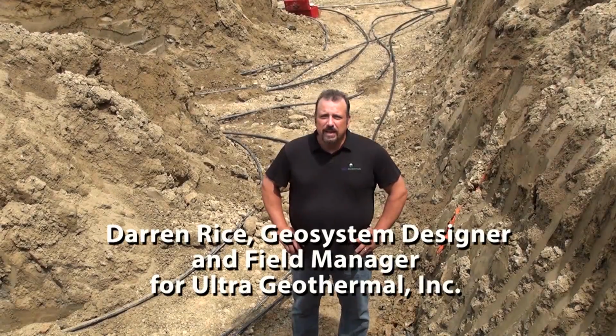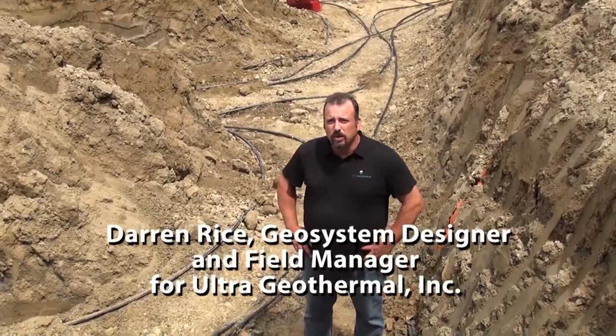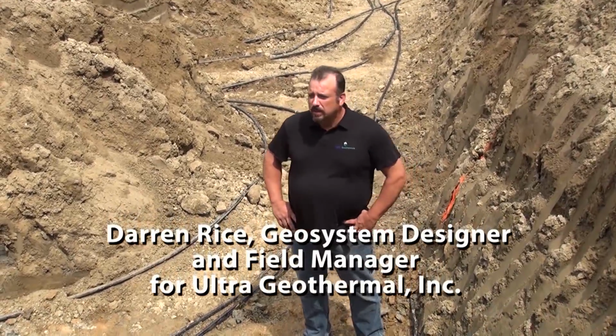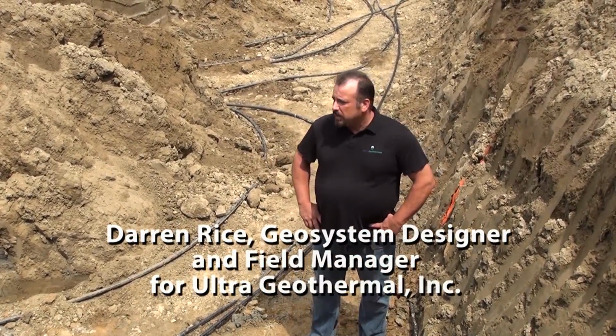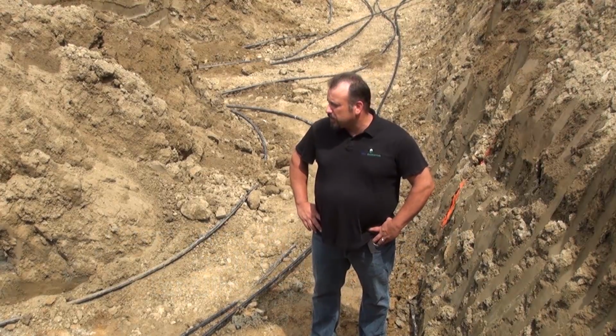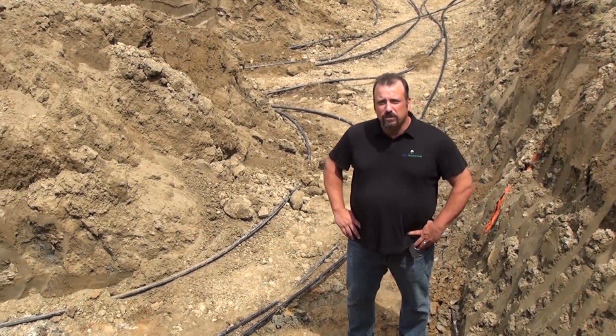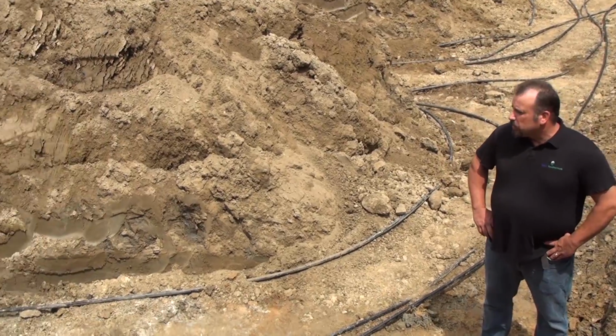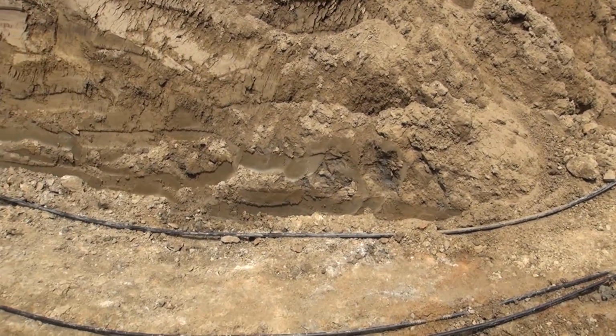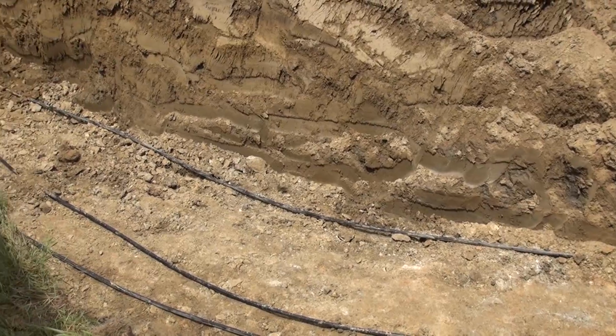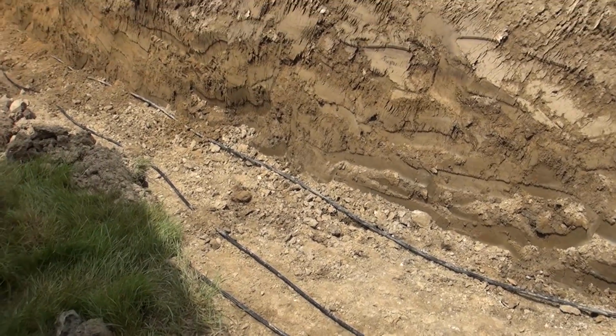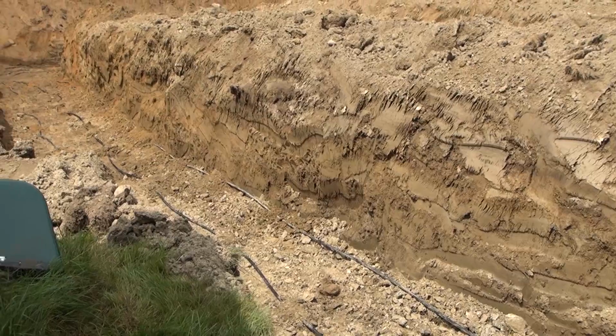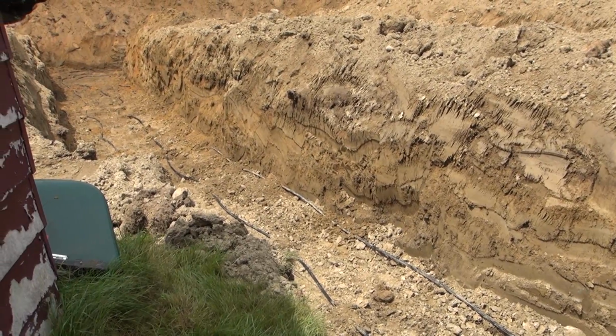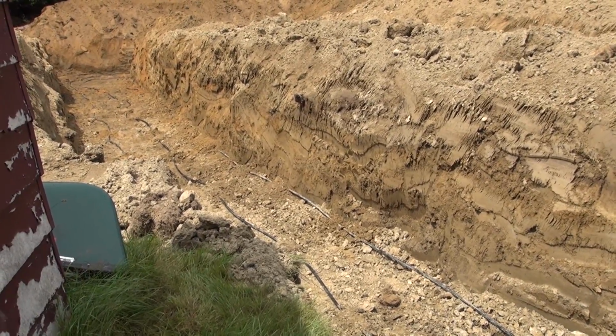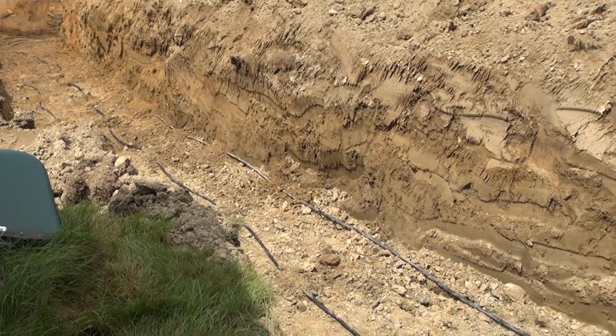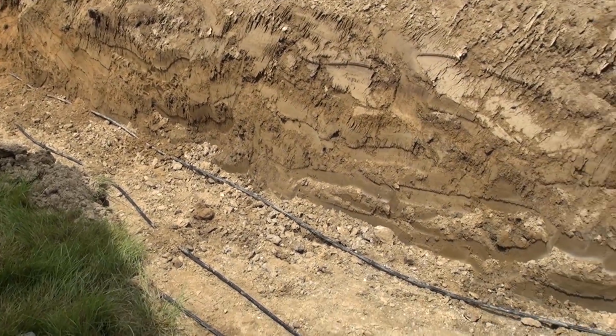With the beautiful property that he has here, he has chosen to go with what they call a horizontal dug closed loop system. Basically, what you see here is a series of pipes that are inserted into the ground, buried roughly 6 feet into the earth. They are filled with an ethyl alcohol and water solution, about 25% ethyl alcohol to water. And this circulates in and out of this ground, again about 6 feet deep, going into the home's heat pump system. And this is the means of heat transfer and cooling transfer for the geothermal system that's being installed here.